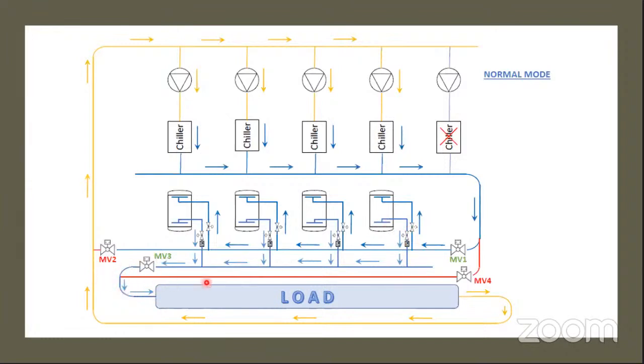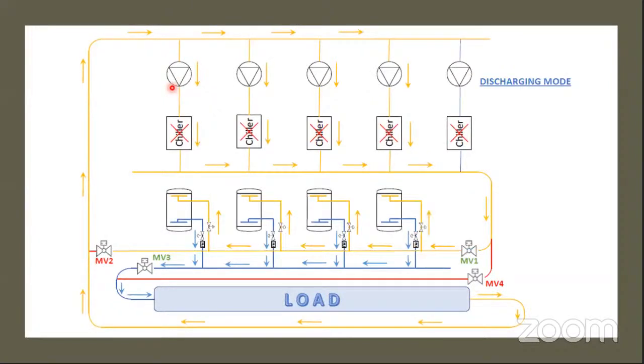and it is going to the load. Then there is a bypass here. This will be used in the other mode. From here it is going to the load, and from the load it is going back to the suction of the primary pump. That's our primary variable schematic. Now, in discharge mode, this is the emergency mode in which chillers are not in operation. Nothing changes, everything remains the same. It's just that the chillers are off.